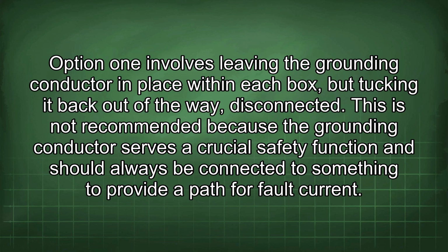Option 1 involves leaving the grounding conductor in place within each box, but tucking it back out of the way, disconnected. This is not recommended because the grounding conductor serves a crucial safety function and should always be connected to something to provide a path for fault current.